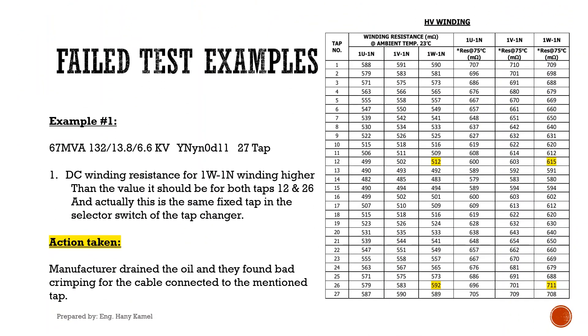From my field test experience, I will share some examples of failed tests. Our first example: a power transformer with 67 MVA, 132/13.8/6.6 kV, YNyN0D11 with 27 taps. The DC winding resistance for the 1W1N winding was higher than the expected value for both taps 12 and 26, which are the same fixed tap in the selector switch of the tap changer. The manufacturer drained the oil and found bad crimping for the cable connected to that tap.